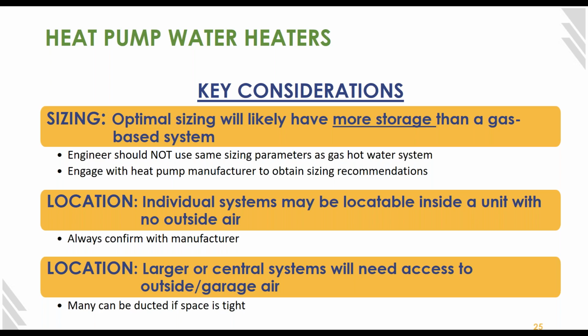With a heat pump, we want more storage and less heat pump capacity, because tanks are cheaper than heat pumps. With gas-based systems, we've been moving toward less storage, all the way to tankless systems with no storage. We actually want to go the other direction with a heat pump water heating system.